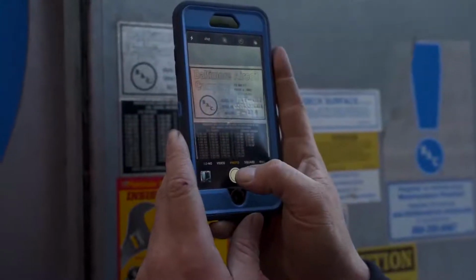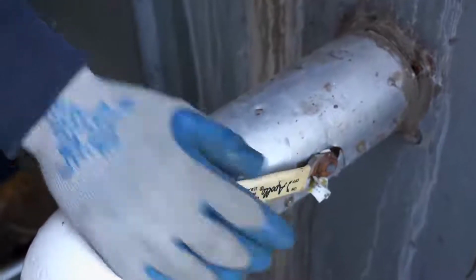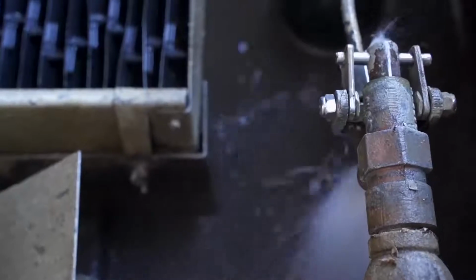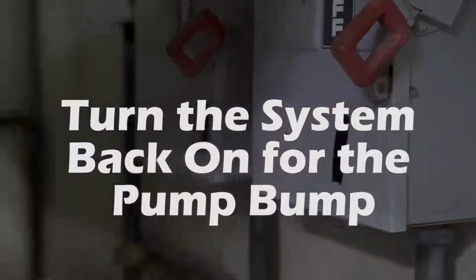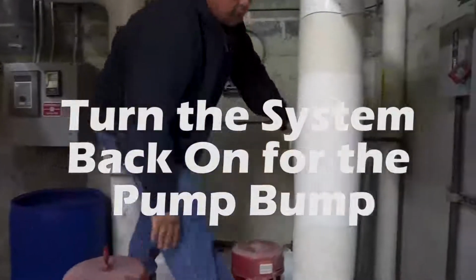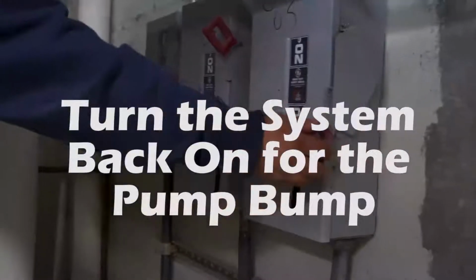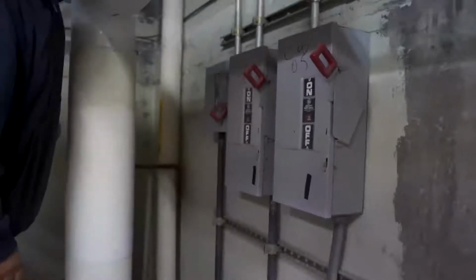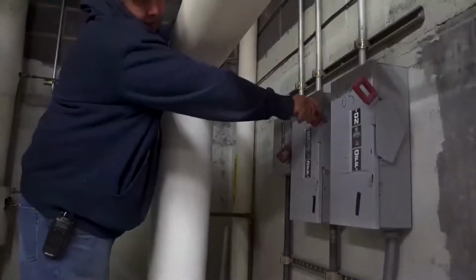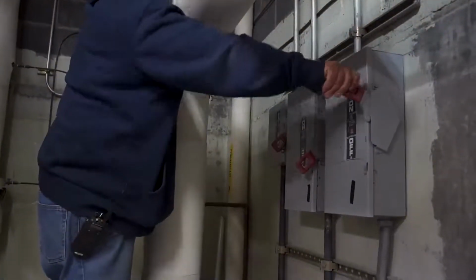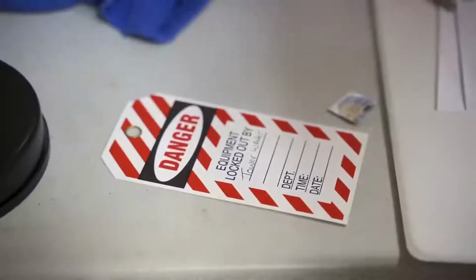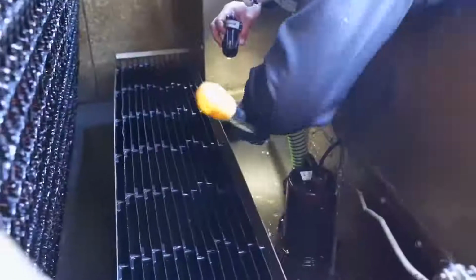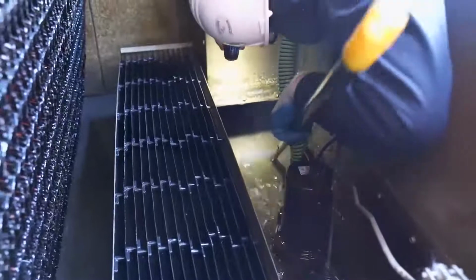Once the cleaning has been completed, begin filling the system by shutting the drain and opening the makeup. For towers where your fire hose cannot provide high-volume water, substitute the bump pump procedure. This is done by removing locks and tags from tower recirculating pumps and having the customer turn them on for 5 seconds, then off. Do this 2 to 3 times. Replace the locks and tags and quickly re-clean the basin of the tower only.